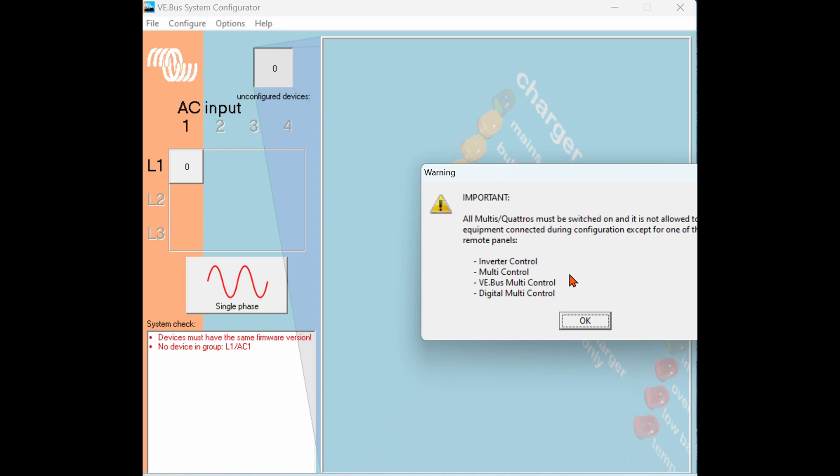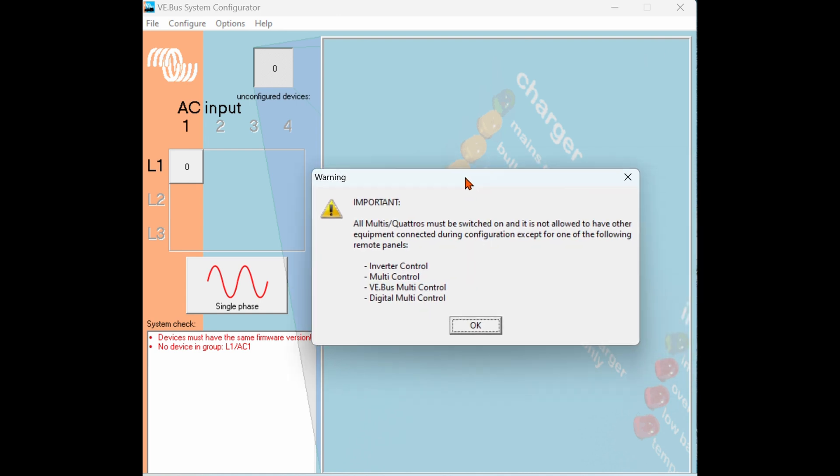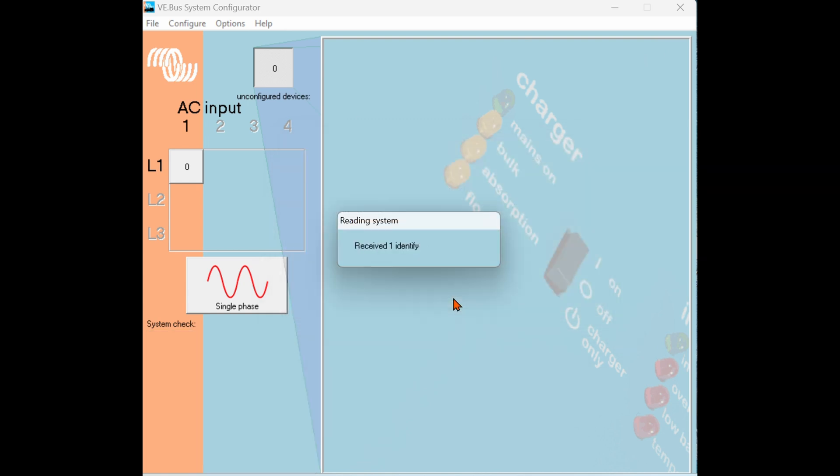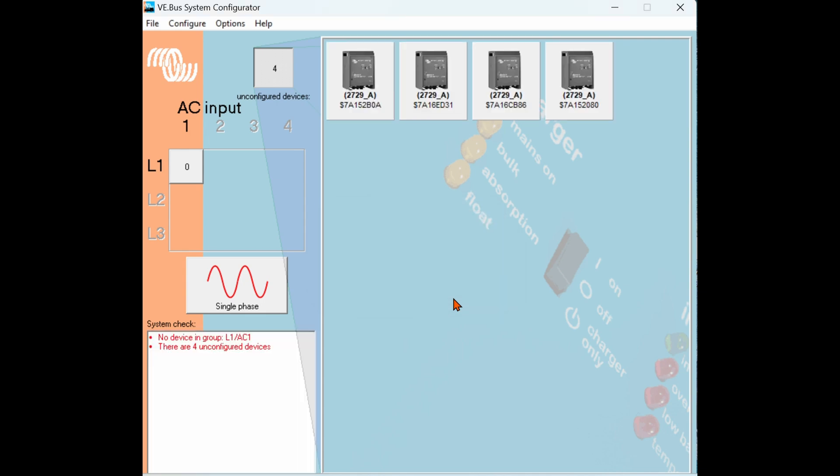It's going to warn us here to make sure we have our inverters connected in the proper sequence, all inverters connected to each other and only the inverters daisy-chained together with the MK3. Each inverter should be on and blinking in an alternating green-yellow fault mode. You should see after scanning the VE Bus Network the software should pull in all the inverters connected within that network, in this case four separate inverters. You can see on the left here the number of unconfigured devices and the corresponding units on the right.